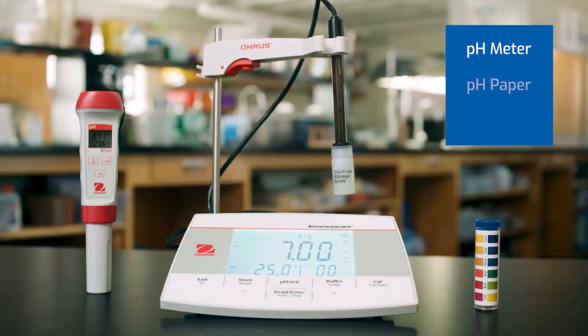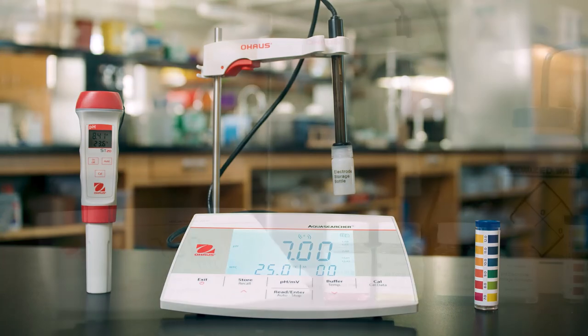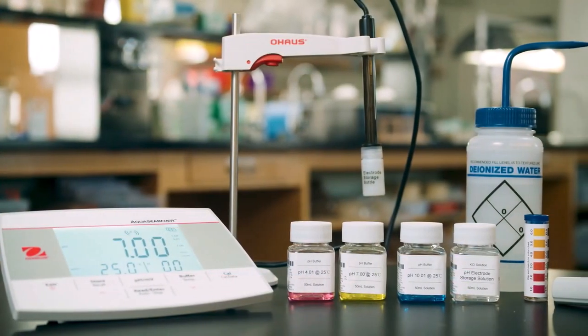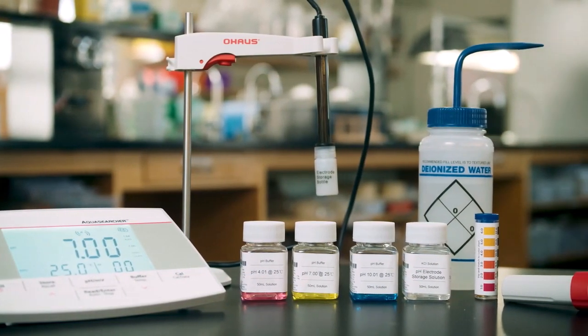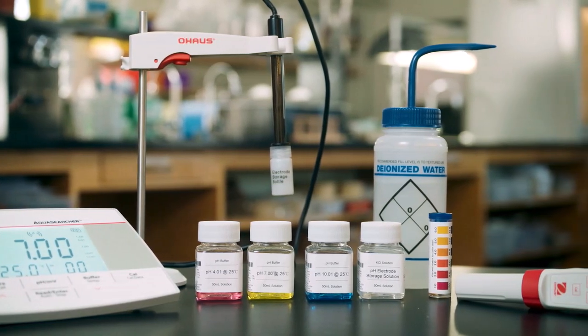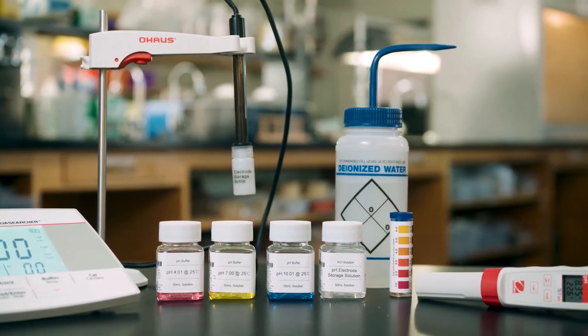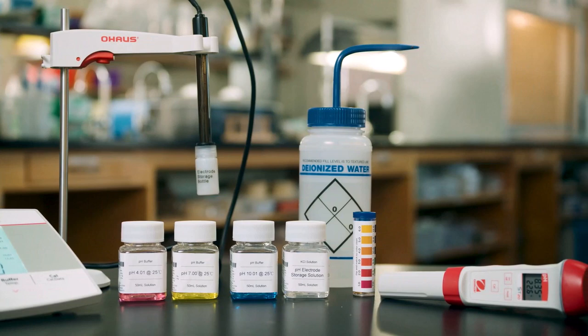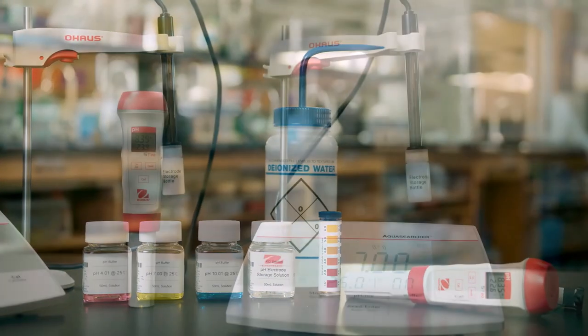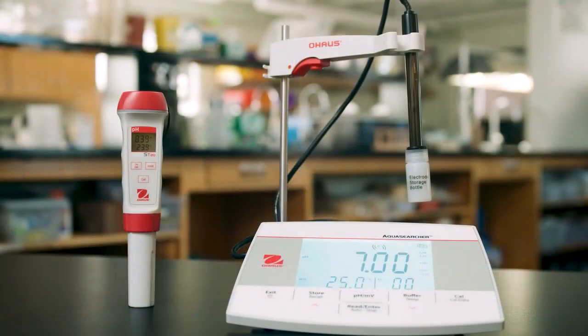A meter, pH paper, or performing a titration can measure the concentration of these ions. Testing pH with a pen or bench meter offers many advantages compared to testing with pH paper or titration. These advantages include more precise and accurate results. Meters can detect pH values with great accuracy. The meters in this video measure with an accuracy of plus or minus 0.05 pH.